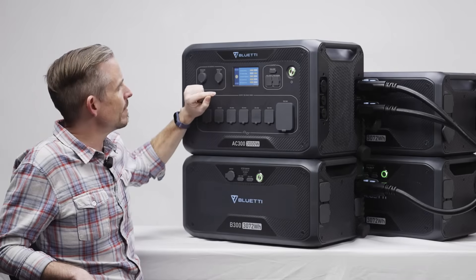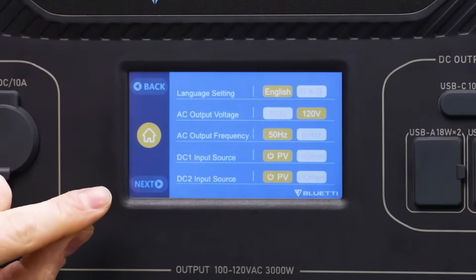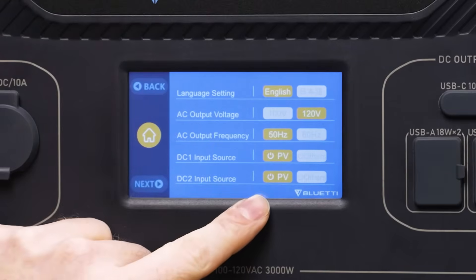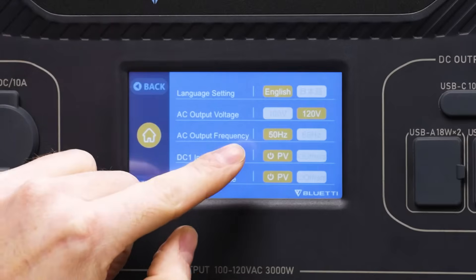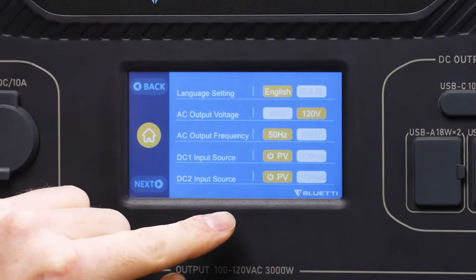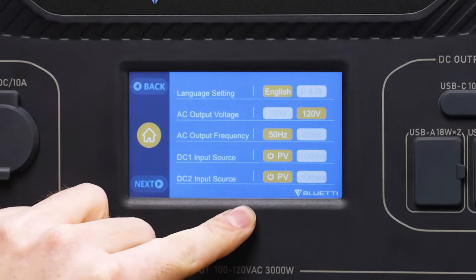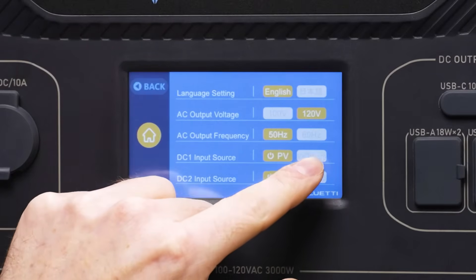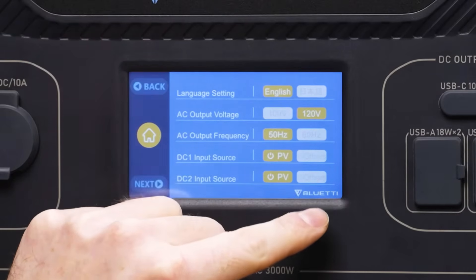Next we have the input source for both DC1 and DC2. If you're using solar panels you want these set to PV, but if you're using any other sort of DC input such as a lead acid battery, you would want it set to others.